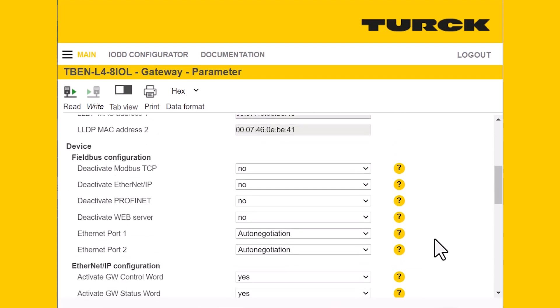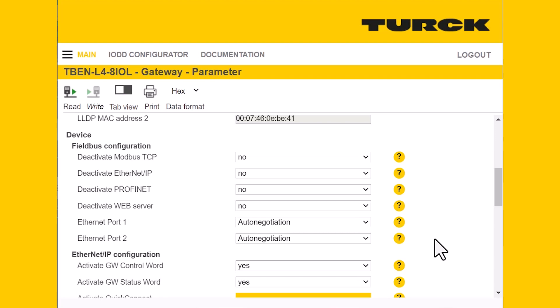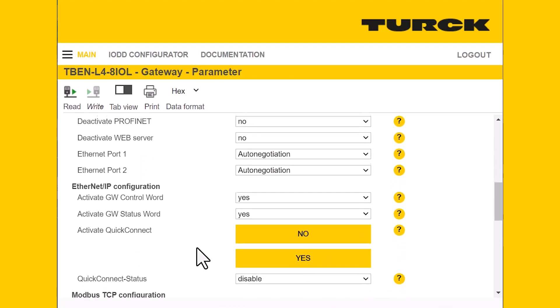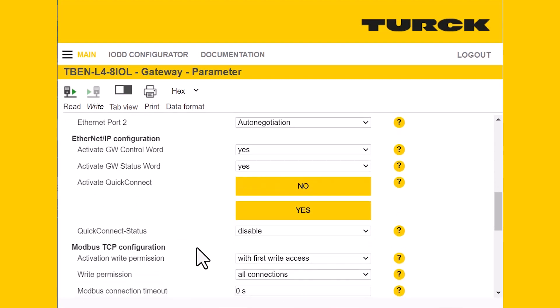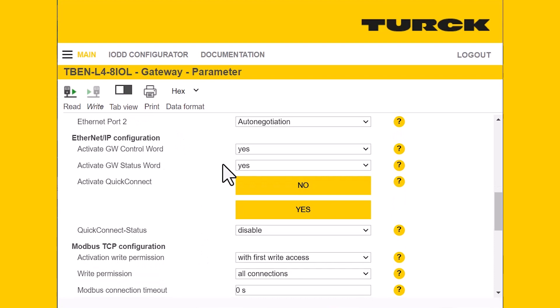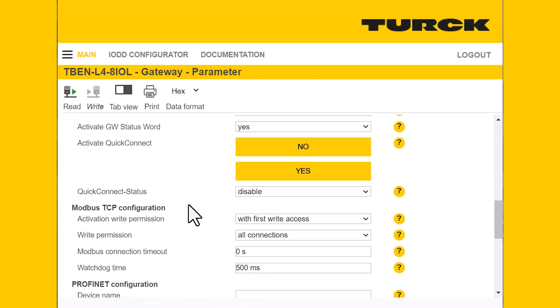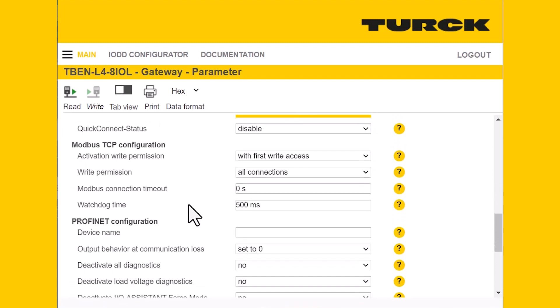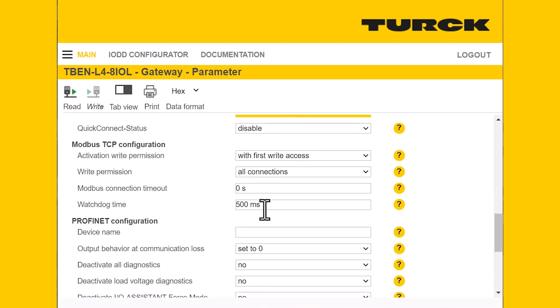We also have parameters for specific communication protocols. We can deactivate any of the specific protocols if we want to, such as Modbus TCP, EtherNet/IP, and Profinet. For EtherNet/IP specifically, we can activate the control word or the status word, or turn those off. For Modbus TCP, we can set our watchdog timer.